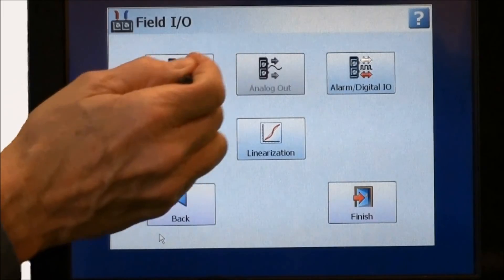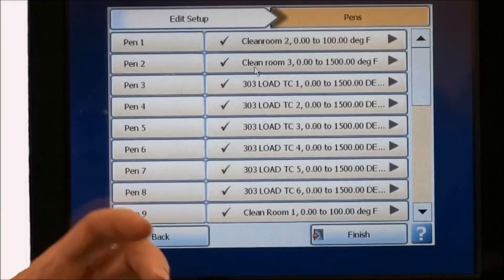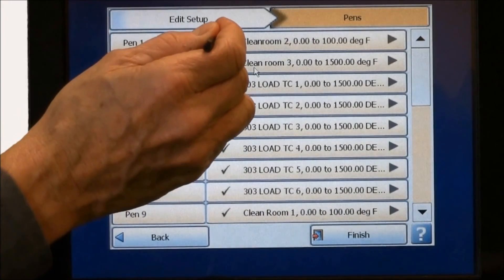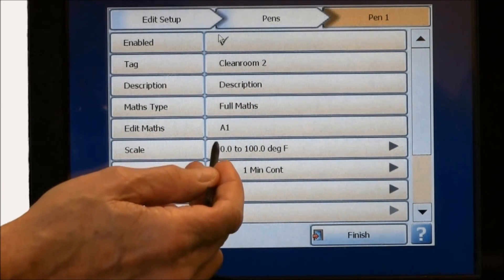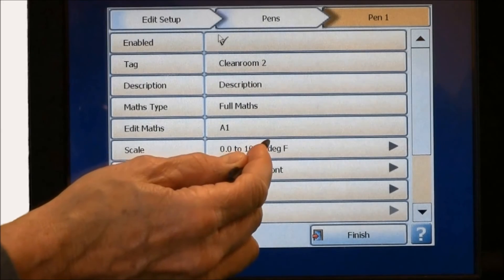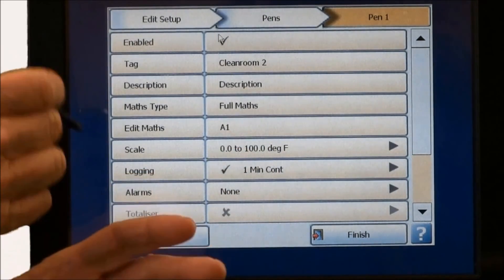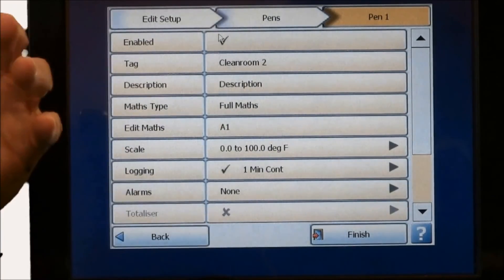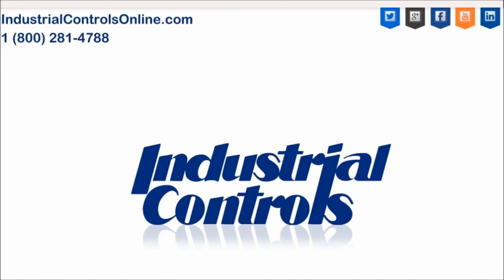From there, you go in and set your pens, which show how each parameter gets displayed on the trend display on the recorder. For example, pen 1 — I put a nameplate in as 'clean room 2', set the scale at 0 to 100 degrees Fahrenheit, and my log rate to the buffer at 1 minute. Everything shown on the recorder can also be done in the Honeywell software, which can then be downloaded on a USB stick and uploaded to the recorder.